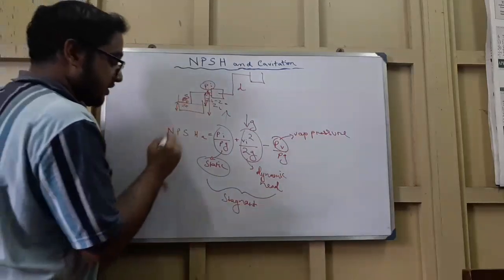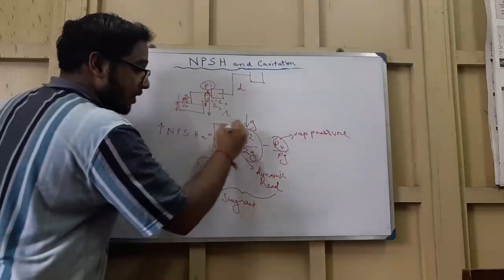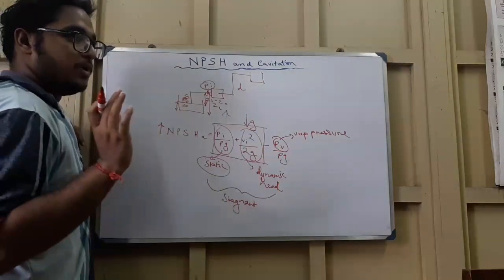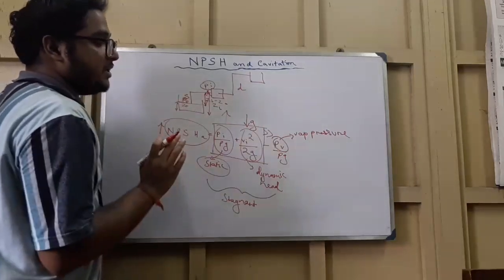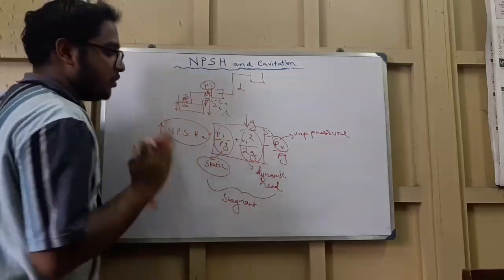To avoid the formation of vapors, this NPSH should be kept as high as possible. For that, the stagnation head must be much higher than the vapor pressure term PV/ρg. If the stagnation head is much higher than the vapor pressure, then NPSH is very high and the tendency to form vapors decreases — meaning the pressure is not comparable to the vapor pressure, so there is no tendency for vapor formation going into the pump.